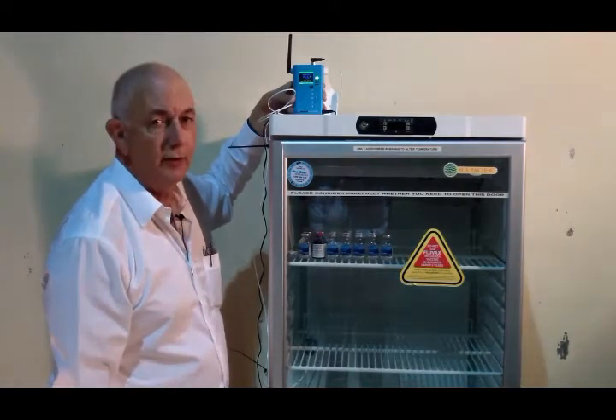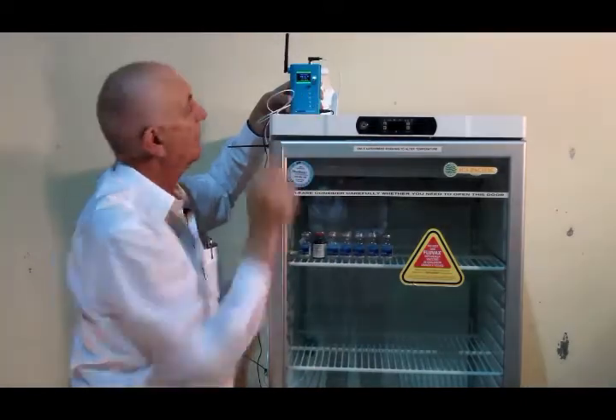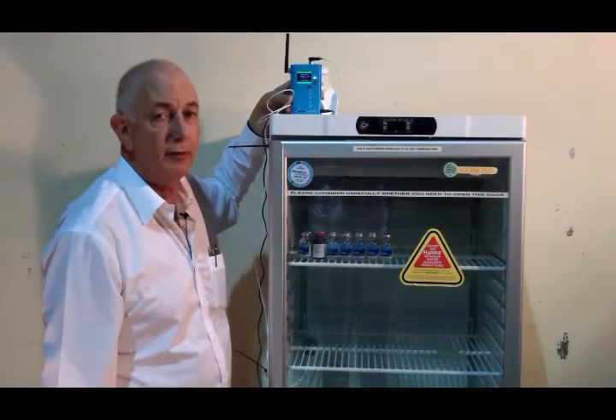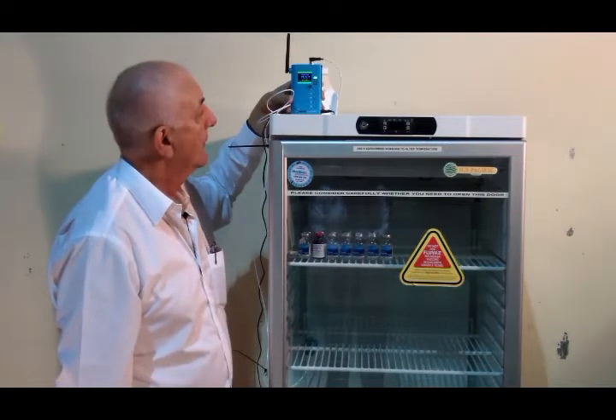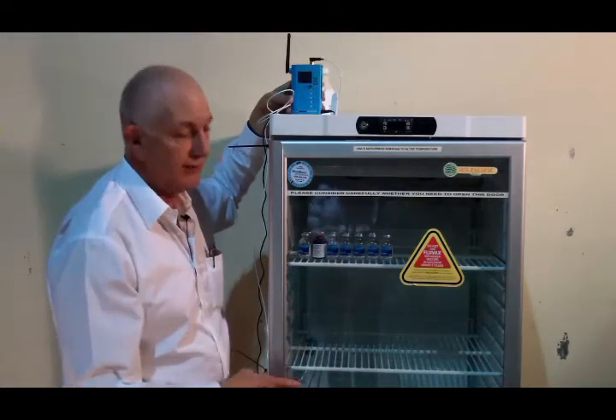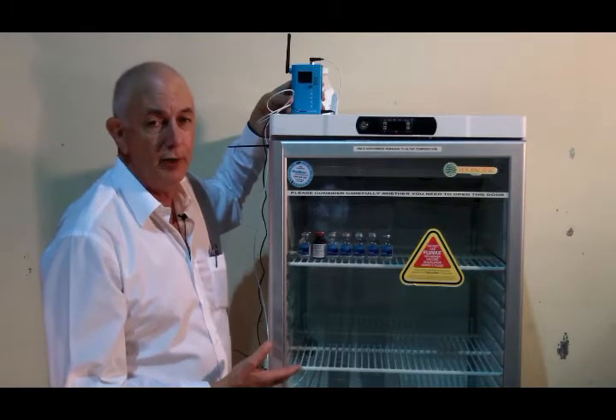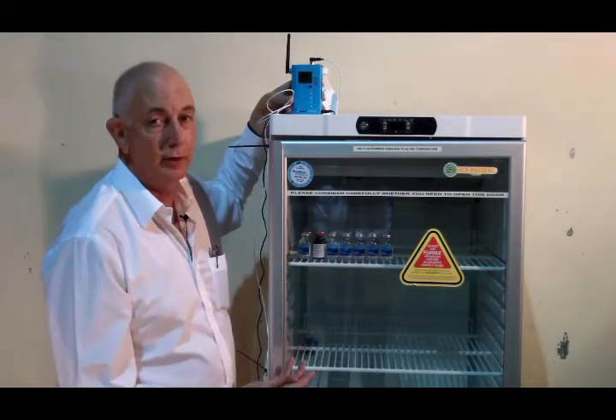After a few seconds, the green LED at the top will flash and the screen will show green and it will also show the temperature of the vaccine fridge. When you've reached that stage, you know that the vaccine monitor is working. It's reading the temperature of your fridge and transmitting it to the cloud. So that's a secure installation.